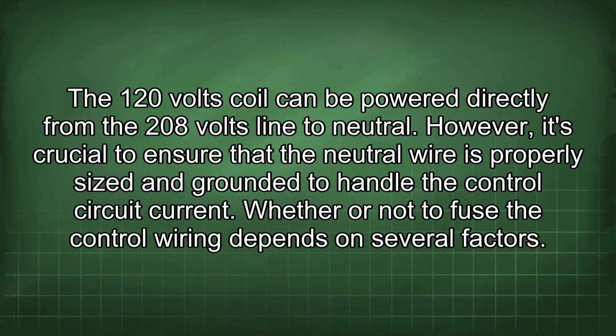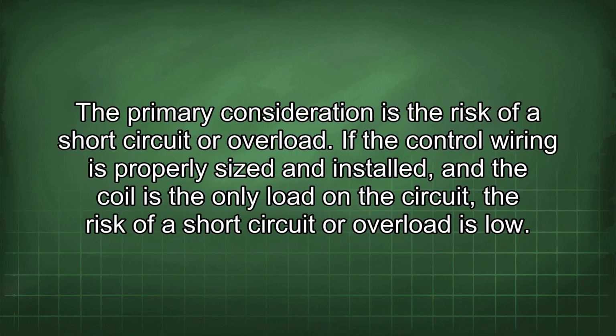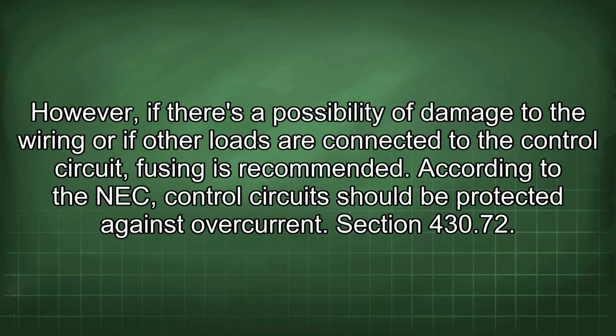Whether or not to fuse the control wiring depends on several factors. The primary consideration is the risk of a short circuit or overload. If the control wiring is properly sized and installed, and the coil is the only load in the circuit, the risk of a short circuit or overload is low. However, if there is a possibility of damage to the wiring or if other loads are connected to the control circuit, fusing is recommended. According to the NEC, control circuits should be protected against overcurrent.